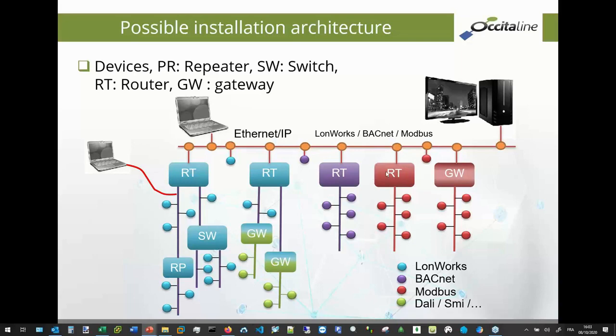An example here, LON. The router exists in LON, the router exists in BACnet. Some devices in BACnet exist on different media, on IP, Ethernet, and the router can also exist in Modbus. And Modbus is a little different because in fact it's not really a router. I would call it a NAT router. In fact, it changes the address.